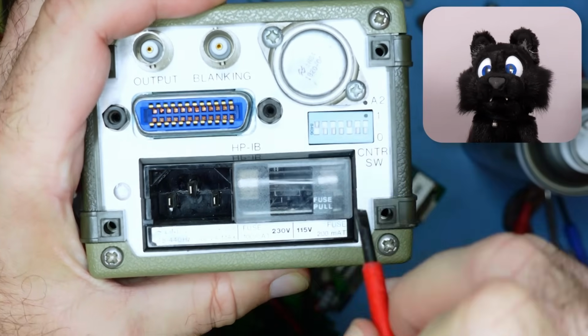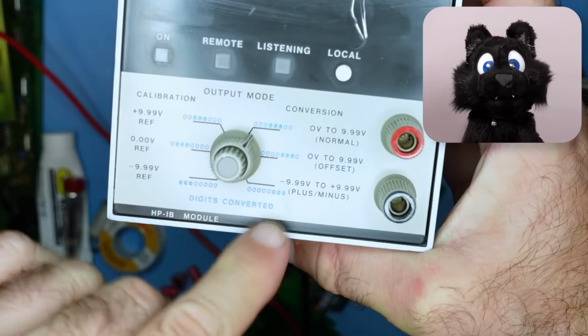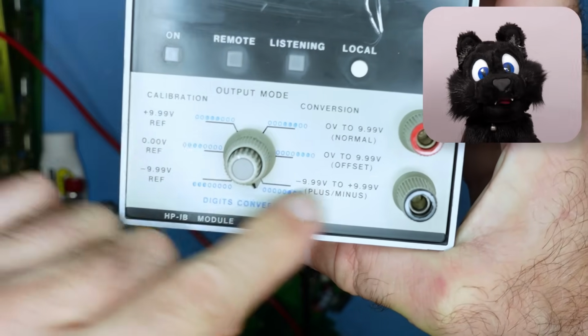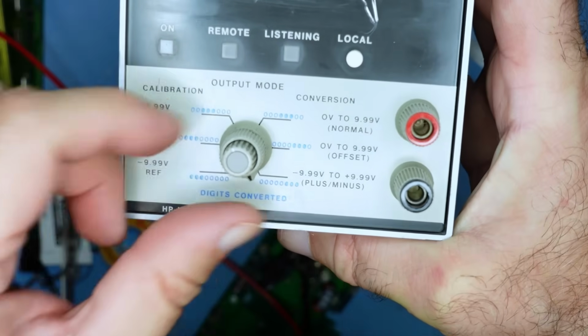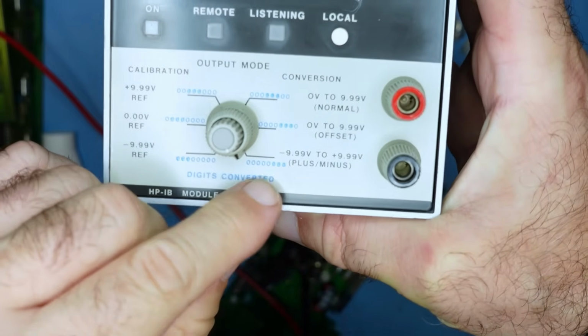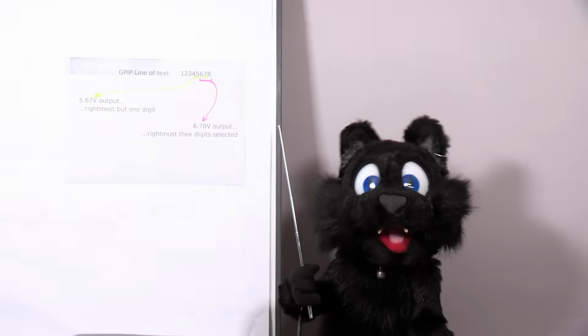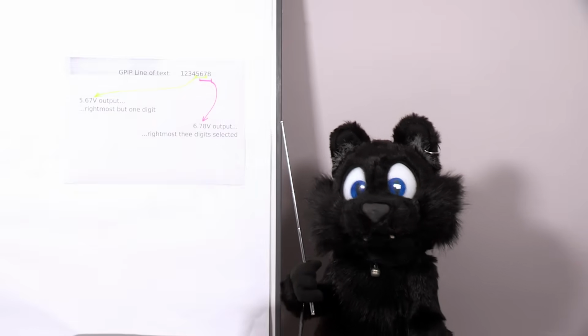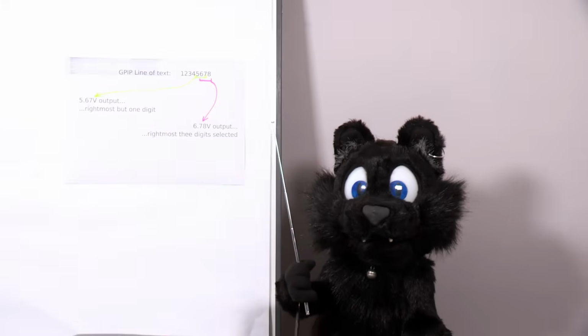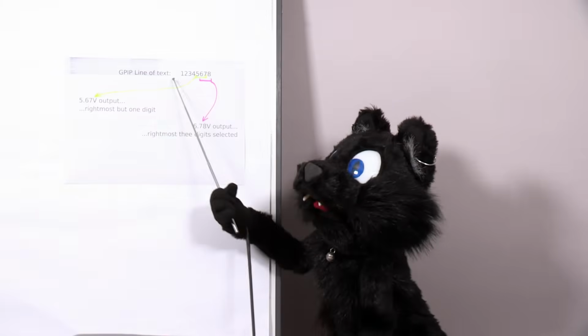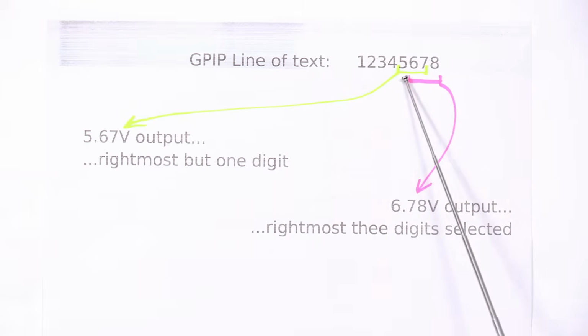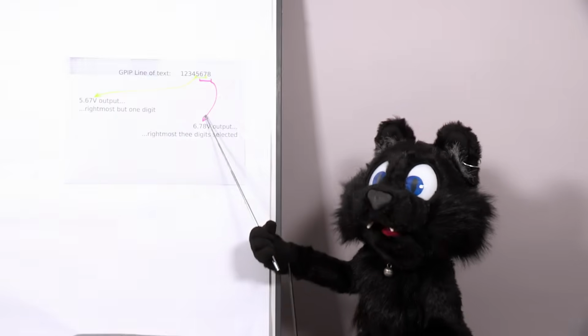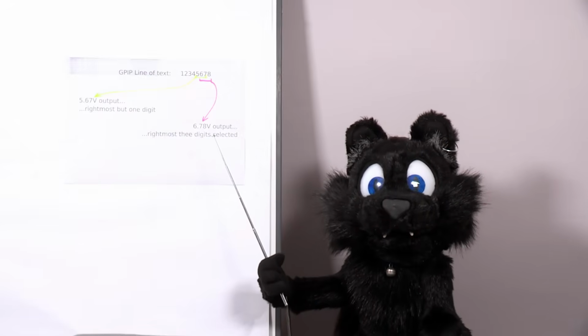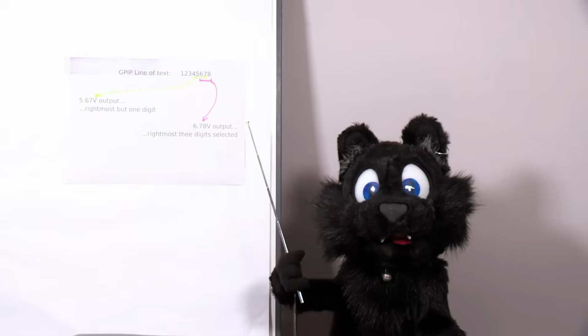To simplify things, I'll put the DA converter in listening mode, that way I can ignore the addressing for now. I want to have plus minus 9.99 volts and I want to read the rightmost 3 digits. What's with the digits? Here's where I had to do some sleuthing. Remember, no manual. As it turns out, the DA converter will read a line of ASCII text and then take 3 digits out of an up to 10-digit number for the output. This way, you can have the meter reporting on the bus and the DA converter can react without any controller in between.